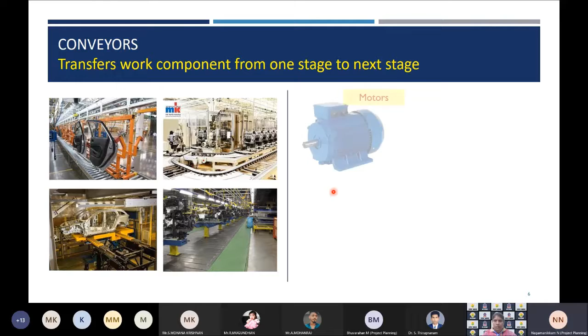All the conveyors are driven by electric motors. Basically, the induction motor is popularly used in conveying systems in the industry, and the motors will be controlled through drives, motor drives we call them. Specifically, VFD drives are being used. The purpose of a VFD drive is to control the motor performance. The control in the sense it will control the acceleration and deceleration of the motor to match the conveyor speed as well as operator safety. There should not be any sudden jerk or impact. It should be smooth enough so that the operator will also feel safe during the work activity.